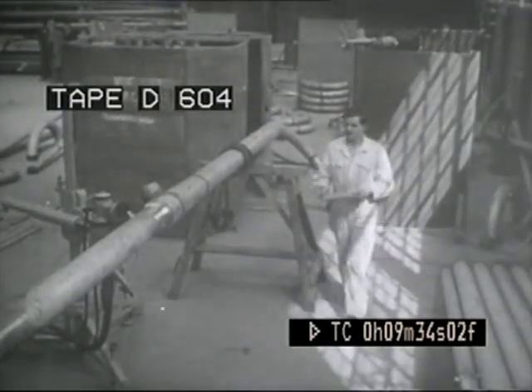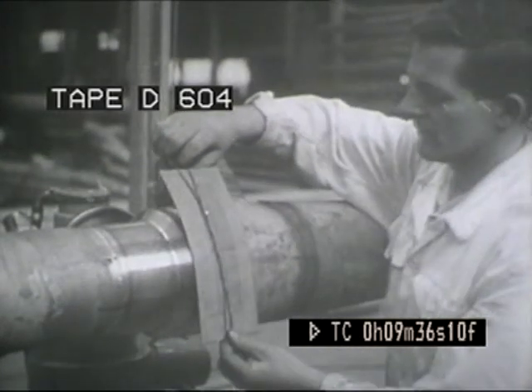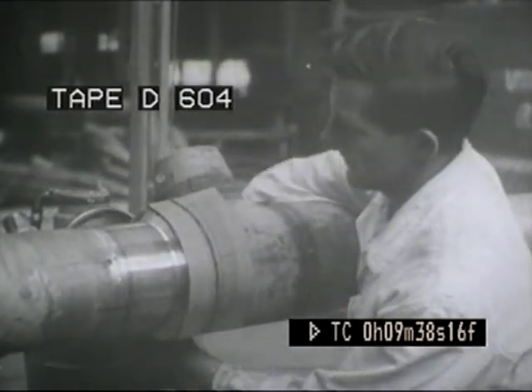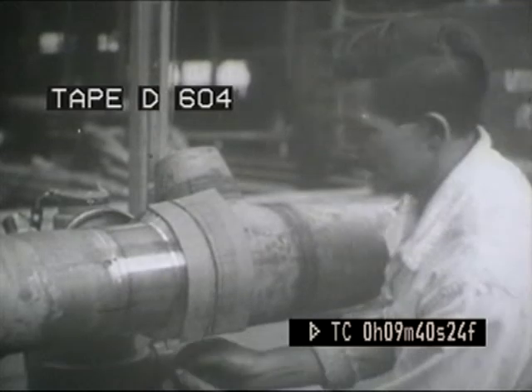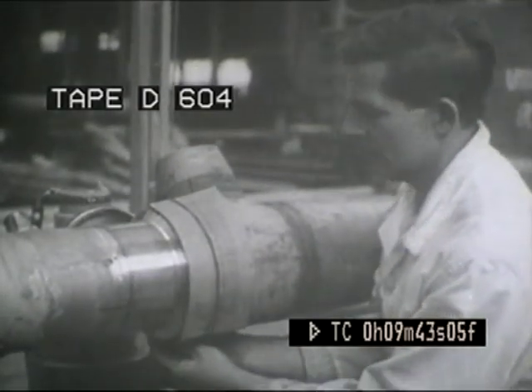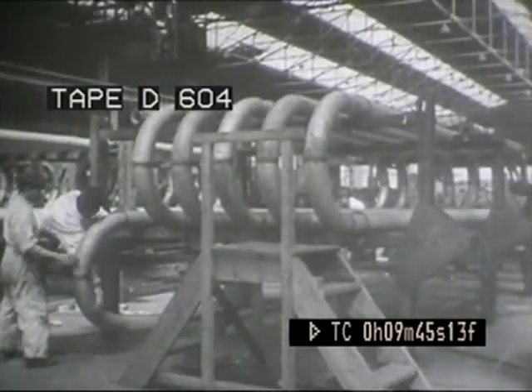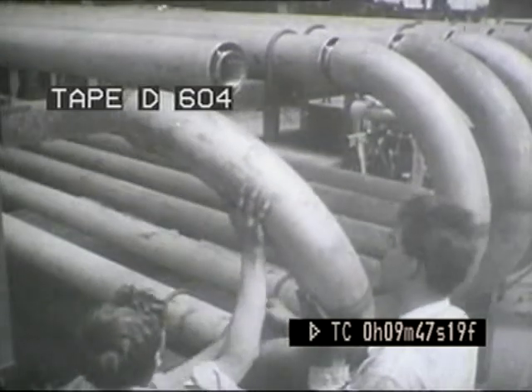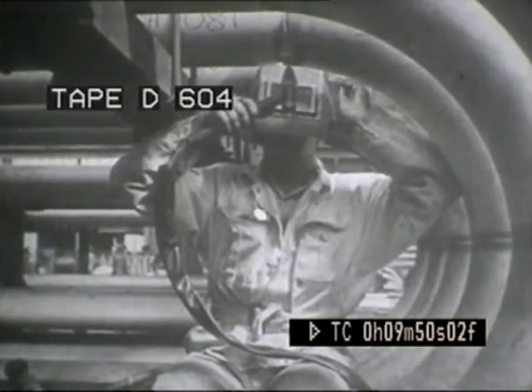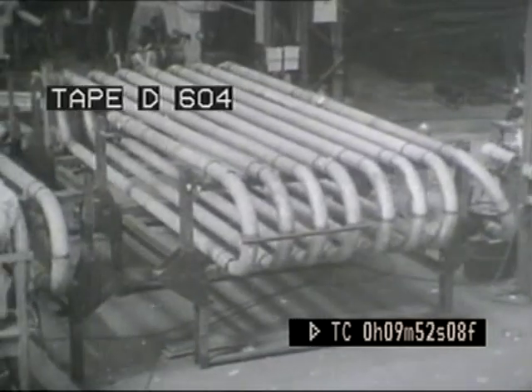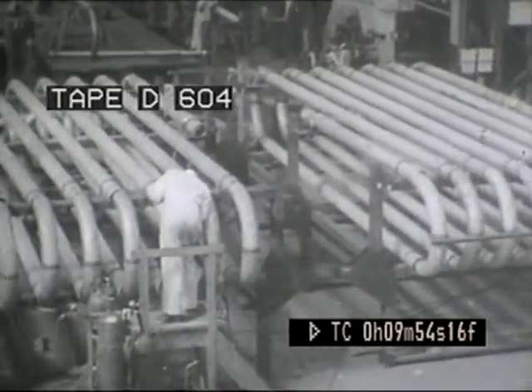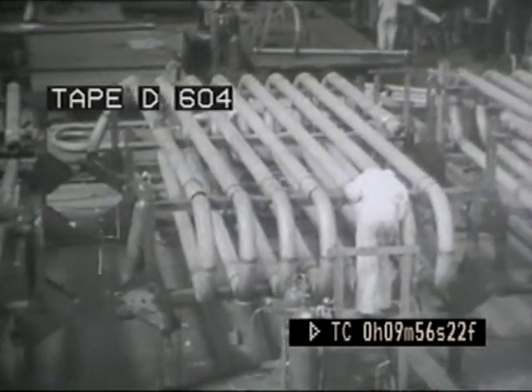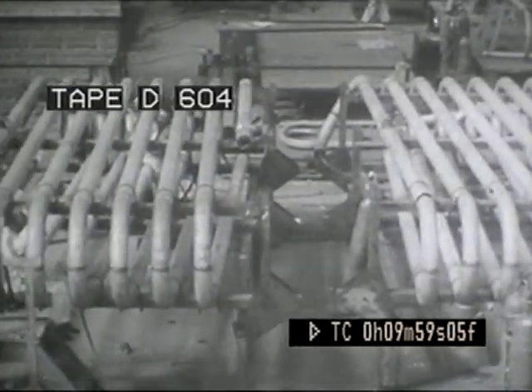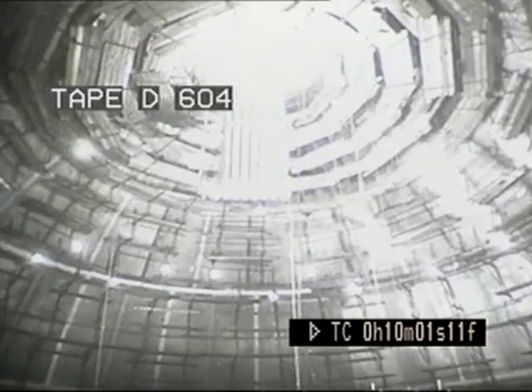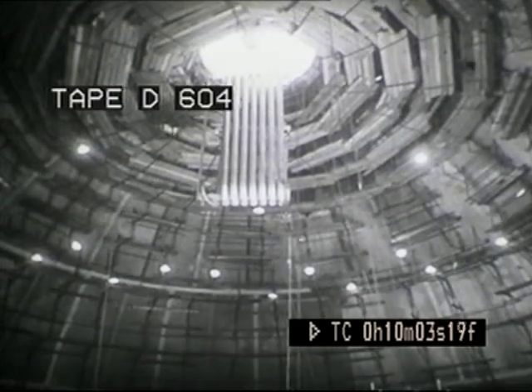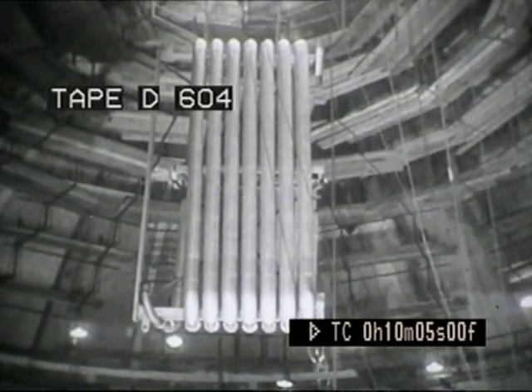Every weld was X-rayed, and for the examination of joins in the concentric tubing, a special technique was evolved, the X-ray beam being angled to prevent the overlap of images of the outer and inner welds. In addition, each section was gas tested. After inspection, sections were assembled on frames to make up complete units and dispatched by road to the site. As with the pumps, the heat exchanger units were lowered into the sphere and down into the vault.